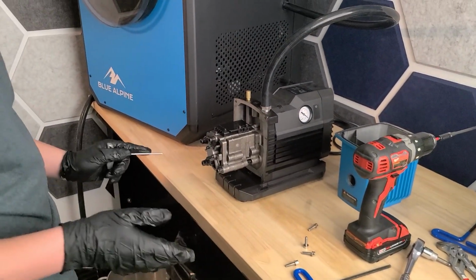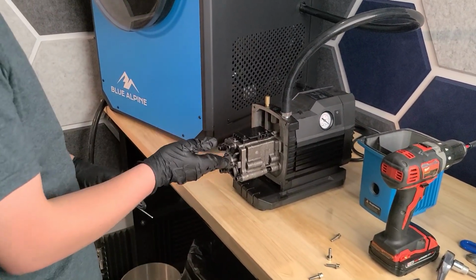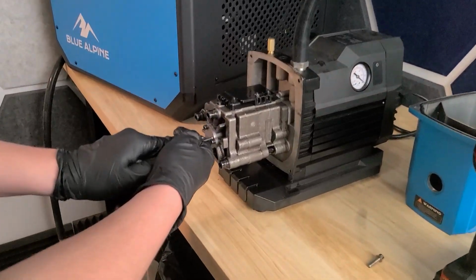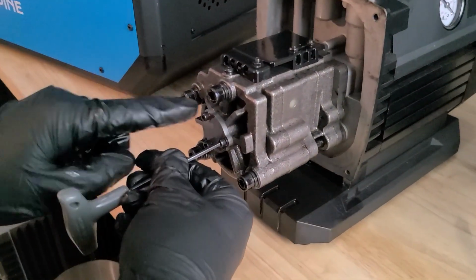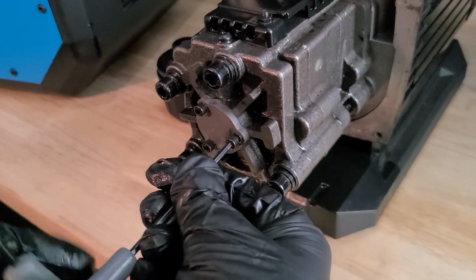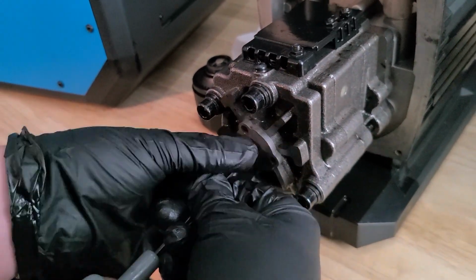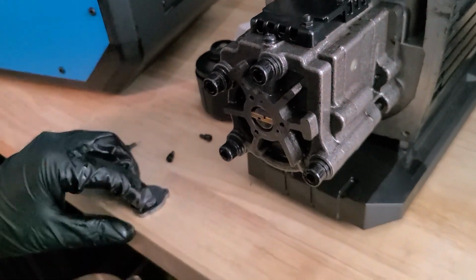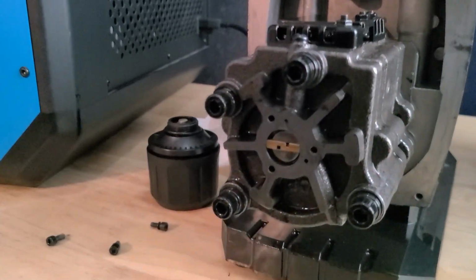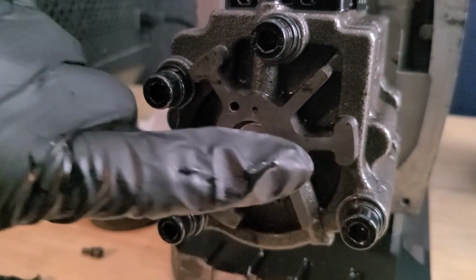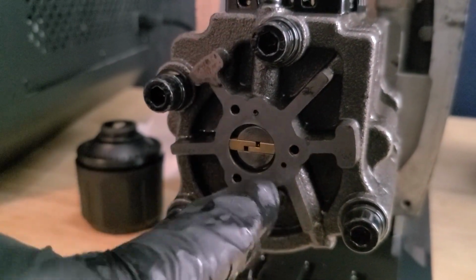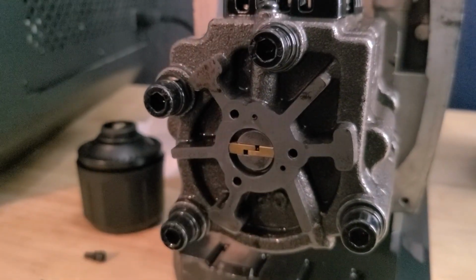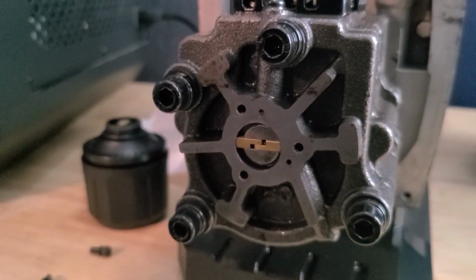Okay, the first thing we're going to diagnose with this vacuum pump is the brass wiper that should be in the front of your vacuum pump. To get to the brass wiper, you're going to remove these 3 screws covering this little plate on the front of your vacuum pump. Once you take those 3 screws out, this piece should just be able to be set to the side. That is what your brass wiper should look like. It should be sitting flush, should not be sticking out at all, and it should have a little gap between the groove. That means that it is separated and is making connection with both sides of the wall.